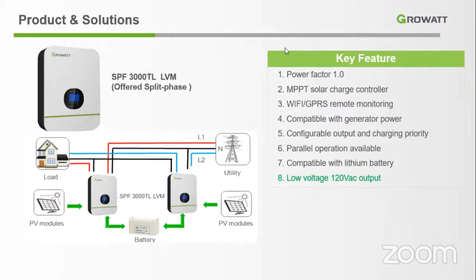Now here we are going to see the parallel mode. As I said, we can connect a maximum of 6 inverters. Maybe you want two per phase to have a three-phase system, or we can connect it single phase, the 6 inverters, to have up to 18 kilowatts. One recommendation from us is to have the same node in the battery. Every inverter has to be connected to the same node in the battery. Also, connect the input to the grid and the output to the load, and see the requirements in the user manual. Later on we can share the user manual with you to start studying it. It's important to follow these rules for the warranty and all those things.